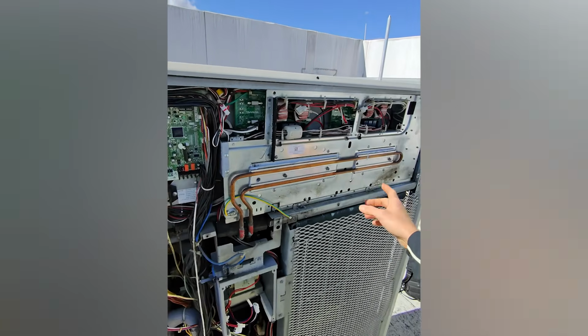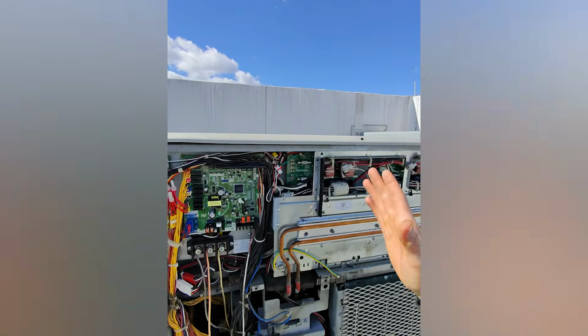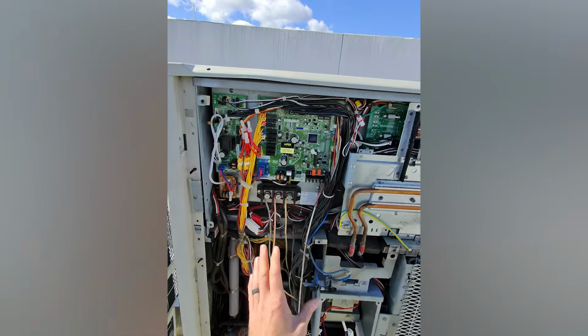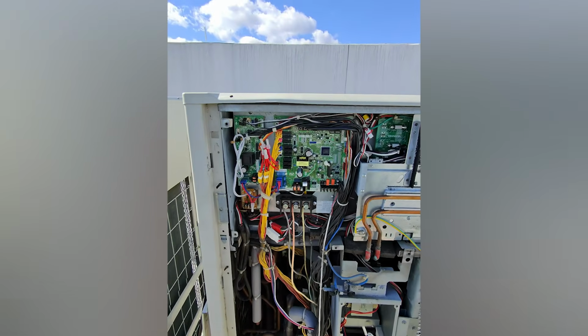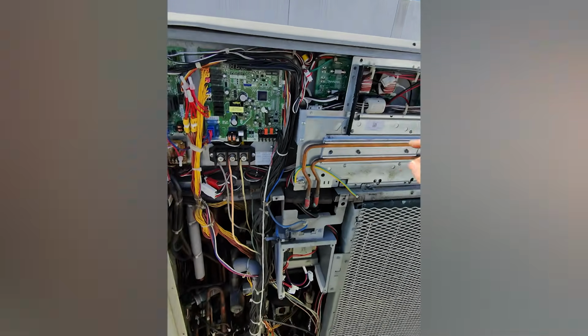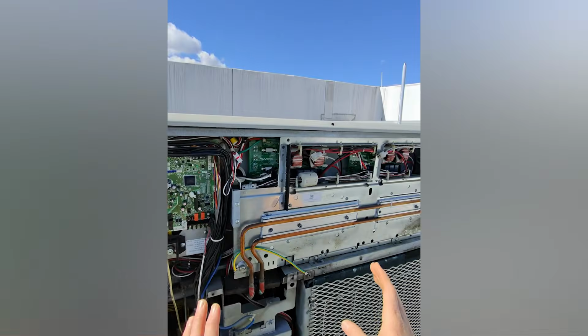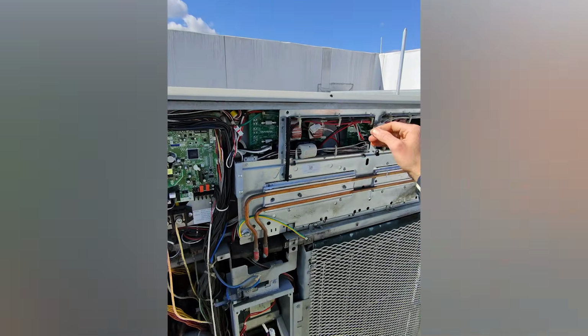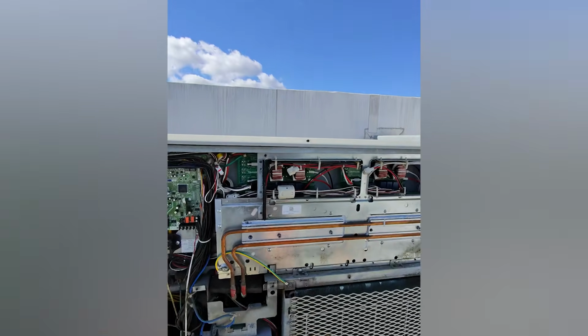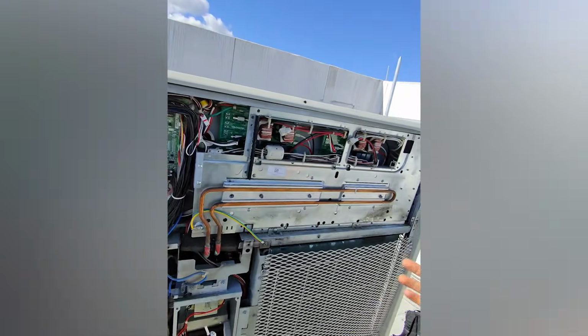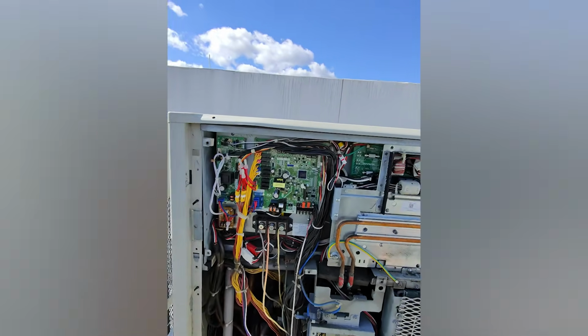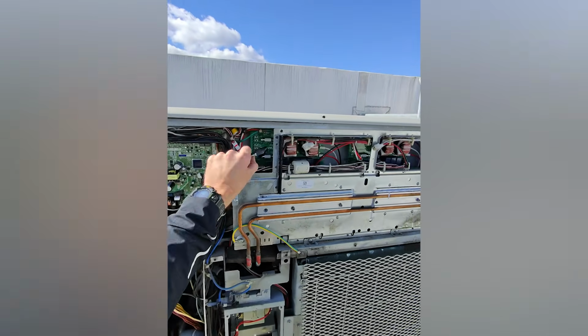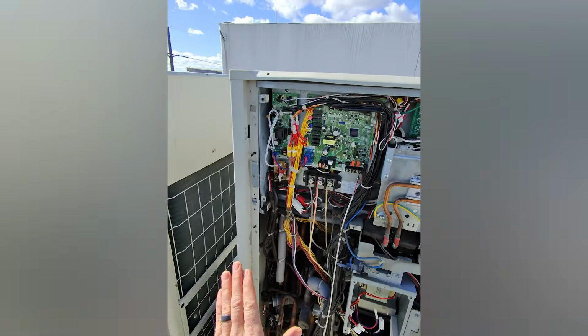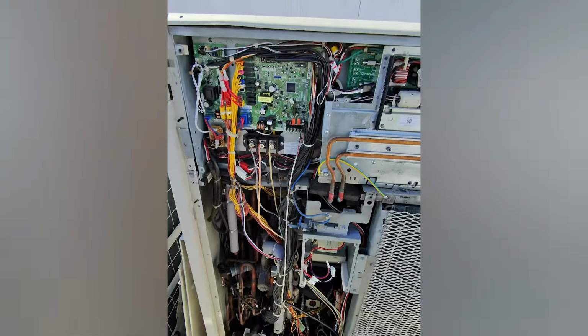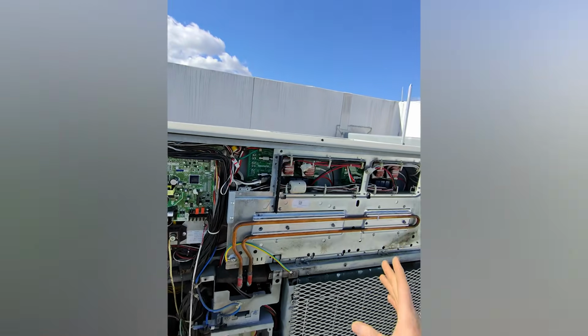Disconnect all the noise filters, compressors, everything, and just isolate it from here down, and at the A1P board, fluctuation stops. When you land the noise filters, but no compressors, no fan motors, no nothing, just noise filters, and disconnect the outs on both sides, still fluctuates. Fluctuates up and down, up and down. But with everything disconnected like this, fluctuations stop. This unit runs just fine, right? It's this unit's problem. Well, the things were okay.